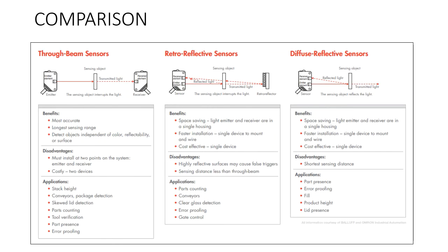In summary: through beam sensors are the most accurate, have the longest sensing range, and detect objects independent of color and reflectability since anything interrupting the path is detected. Retro reflective sensors are space-saving because emitter and receiver share the same housing, allow faster installation, and are cost-effective since the retro reflector requires no wiring. Diffuse reflective sensors are even more compact — no retro reflector needed — and installation is very fast with only one device to mount.